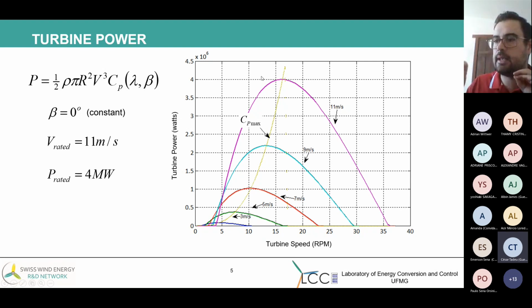But when we say rated power of the turbine, in fact we are talking about the rated power of the generator. In this case, the generator is designed for 4 megawatts, and then the rated speed is 11 meters per second. Another turbine, I can have 5 megawatts with a rated wind speed of 12 meters per second. This is a design. This is the product choice. Then the turbine will be chosen.